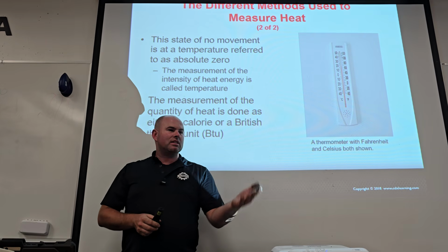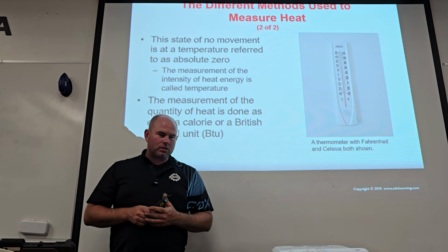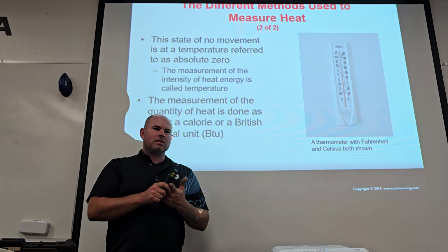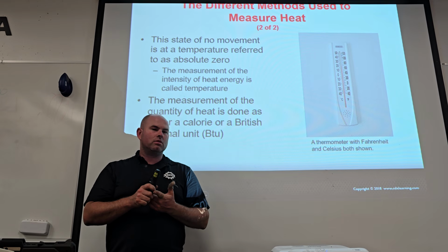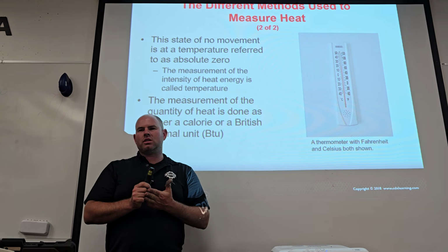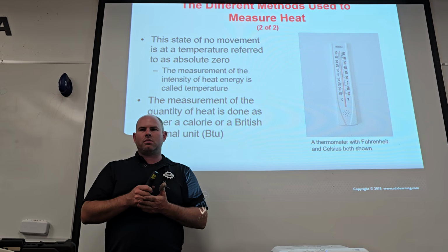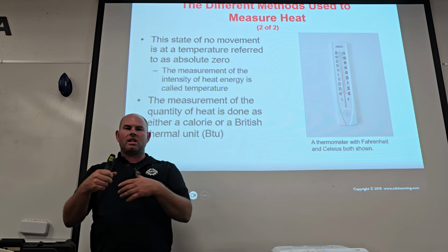So when they go to size an AC, they have to know in BTUs. So yeah, you might see a 5,000 BTU. It's more traditional if it's something bigger to be a ton. 1 ton AC is 12,000 BTUs. 2 tons, 24, 3 tons, 36, right? So if you need a 3 ton AC, 36,000 BTUs, that means it has the ability to move 36,000 BTUs.